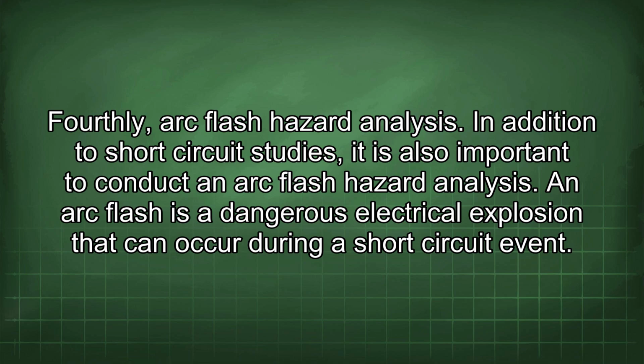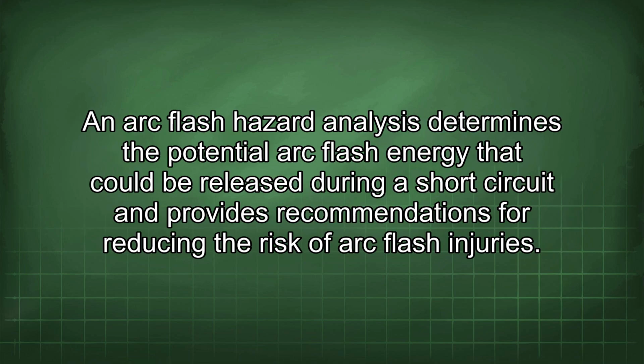Fourthly, arc flash hazard analysis. In addition to short-circuit studies, it is also important to conduct an arc flash hazard analysis. An arc flash is a dangerous electrical explosion that can occur during a short-circuit event. An arc flash hazard analysis determines the potential arc flash energy that could be released during a short circuit and provides recommendations for reducing the risk of arc flash injuries.